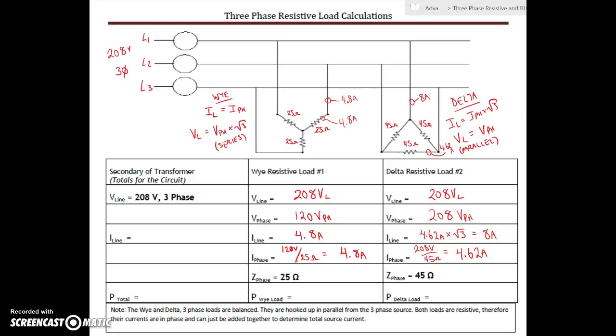Down here for the power, we can find our power by taking our line voltage—so we've got 208 volts—times our line current of 4.8 amps times root 3, and that gives us 1729.27 watts.